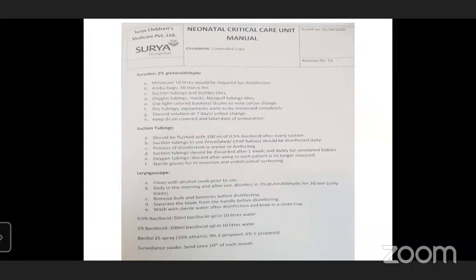Okay, if you look at the top one, the Korsolex, the 2% glutaraldehyde, minimum 10 liters you need, because all your equipment - the small equipment, oxygen tubing, mask, everything - should be completely immersed and submerged in that. So you need to have a particular level. This would roughly come up to 3/4 of a normal bathroom bucket - apna bathroom ka jo bucket, roughly 3/4 of that will get filled.